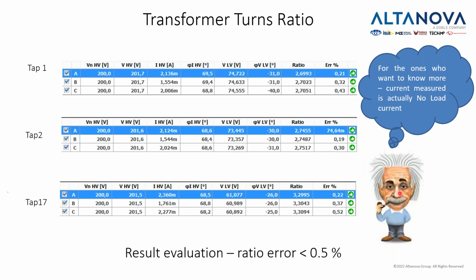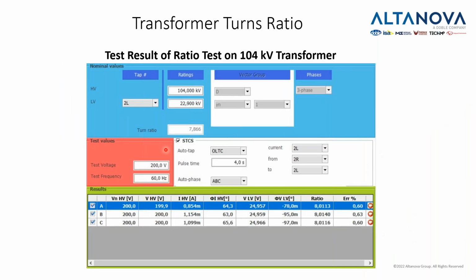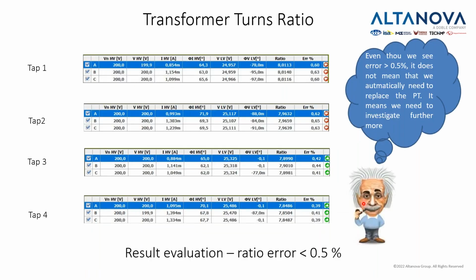And Mr. Einstein here tells us also that we can observe this parameter here. So this is the generated voltage and the generated current. The current which we generate is actually a no-load current, but we will talk about the no-load test a little bit later. Here we have another example where we also did the test, and we have values slightly above 0.5: 0.6, 0.63. So these are the errors above 0.5.